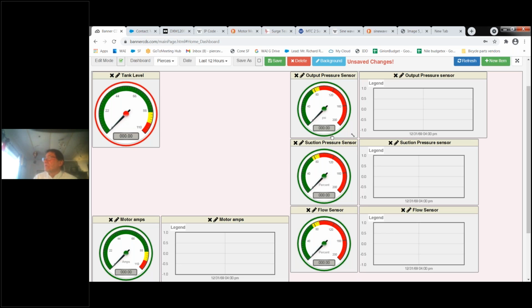What we have here is a typical dial. We can have a bar chart. This is a data over time trending chart. My preferred way of displaying data is twofold. I'll give you the instantaneous data on the graph. Here we're saying output pressure is green up to about 75%, and then from 75% up to 90%, it's yellow, and above that, it's red. I can also put a green and red light here that tells me when I go into the red zone if I want to. This is the data over time chart. So it tells me what's going on over the past, some history, if you will. So I get the instantaneous data and I get the history. I like this. Other people may like it a different way.